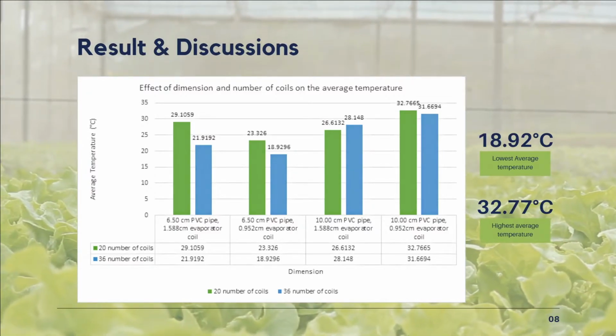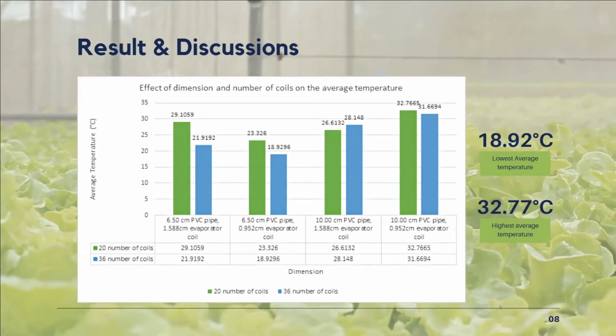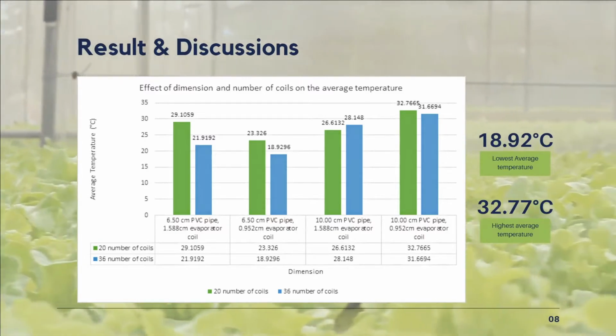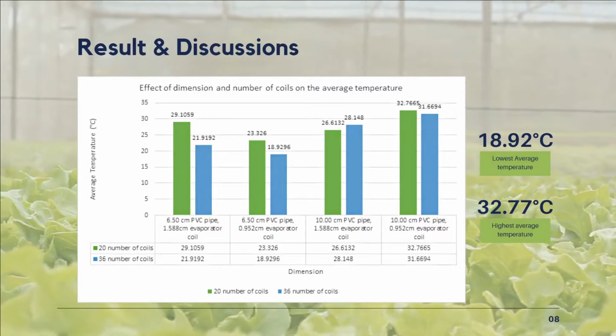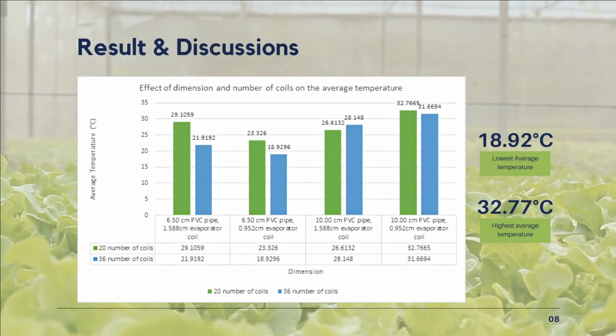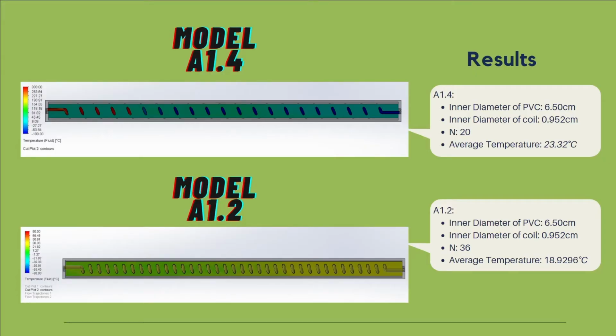Other than that, based on this result, it is shown that the most effective model is the model A1.2, which has a 6.5 centimeter diameter of PVC pipe, 0.952 centimeter diameter of helical coil, and number of coil of 36. The figure shows the distribution of refrigerant 134A and water in the cooling tower of both A1.4 and A1.2. The level of the temperature is shown in the form of temperature gradient. Based on the result shown, model A1.4, which has a 6.5 cm diameter PVC pipe, 0.952 cm diameter of helical coil, and number of coil of 20, achieves 23.33 degrees Celsius, while model A1.2, as we mentioned earlier, achieved 18.93 degrees Celsius.